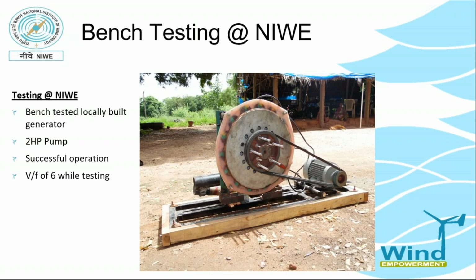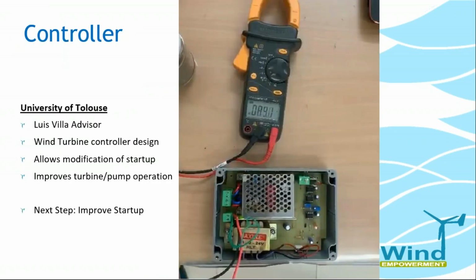We have a 440 volt generator and motor that are working technically at 50 hertz. So the voltage over frequency has a ratio which, in the case of India, is 8.8. As long as the generator is able to deliver the power at the same ratio, then we're operating just as a variable speed drive would operate a motor in an industrial setting. So a standard induction motor, if it's operating with a variable speed drive, will operate correctly and it will not burn. Yeah, so this is the way the system is working in our case.